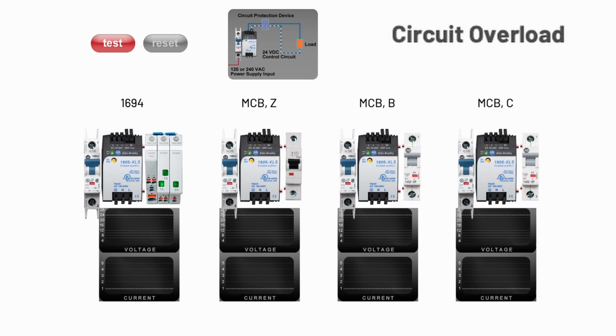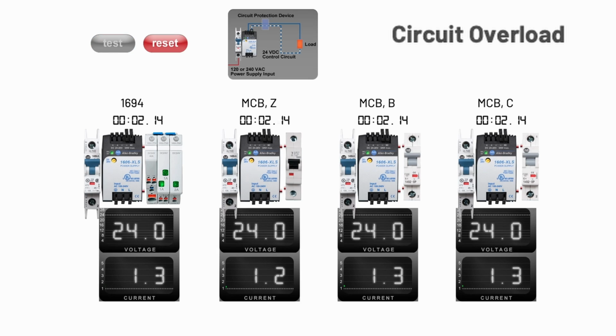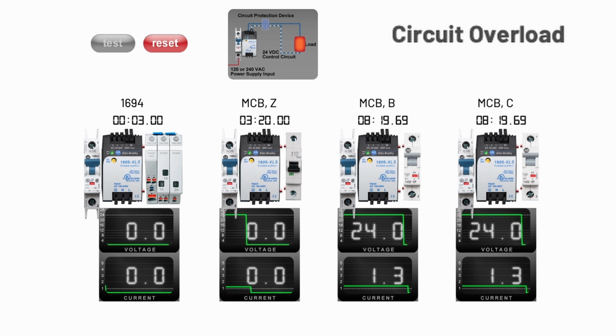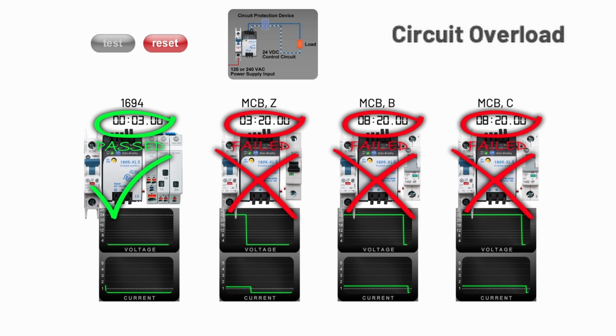The third simulation is looking at the performance in an overload situation where the field device is exceeding the 1 amp current draw. In this case, the 1694 ECP shut down the output after about 3 seconds, but it takes approximately 3 to 8 minutes for the miniature circuit breakers to trip. The reason for that goes back to one of my opening statements regarding the fact that AC circuit breakers have thermal characteristics that require extended time to detect an overcurrent condition.